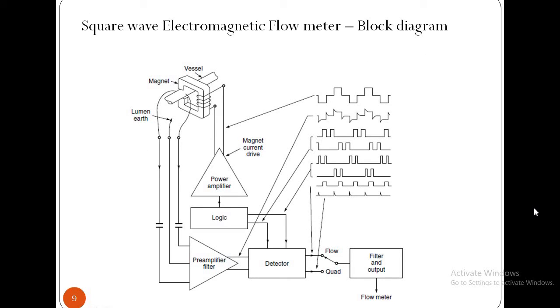The figure shows a block diagram of a square wave electromagnetic blood flow meter. The flow transducer consists of an electromagnet which provides a magnetic field perpendicular to the direction of flow, and lying within the field are a pair of pickup electrodes whose axes are perpendicular to both the field and the flow axis. The electrodes may be in contact with either the flowing blood or the outer surface of the blood vessel carrying the flowing blood. The former is called cannulating flow meter and the latter cuff flow meter.